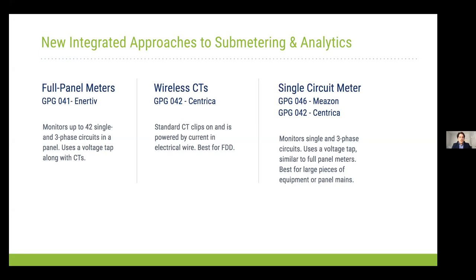The third category we've seen is the single circuit meter. These tend to be higher accuracy CTs, but they have a larger footprint, so they might not be the best if you want to monitor all the loads in a panel. They require a voltage tap and CTs, and the best application is probably for large pieces of equipment or monitoring the mains of a panel.